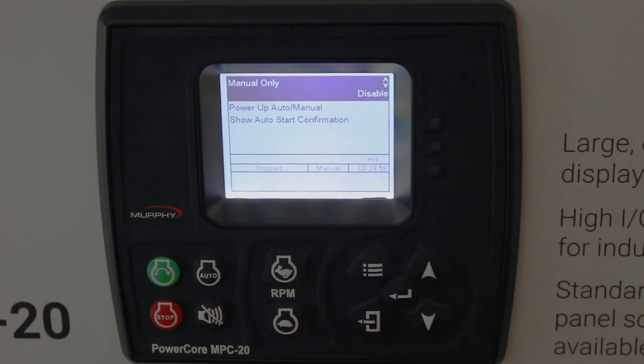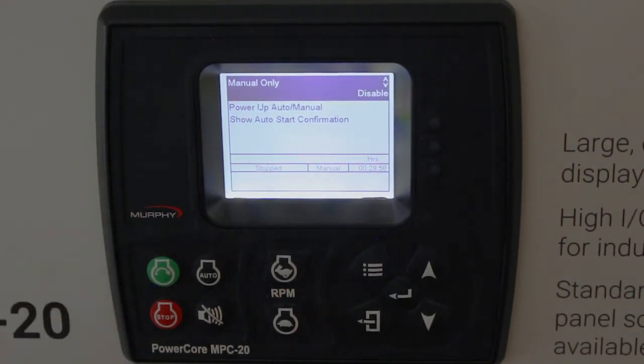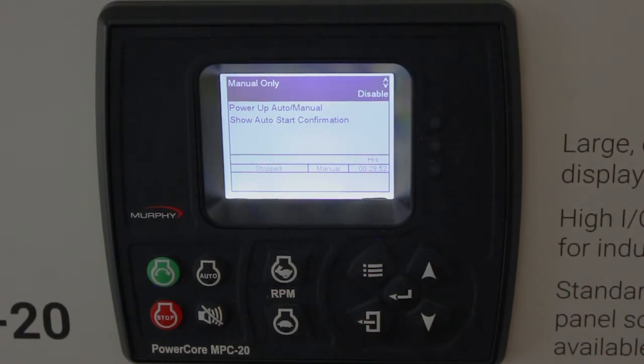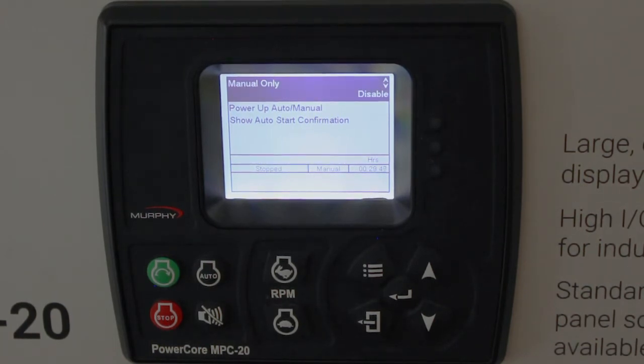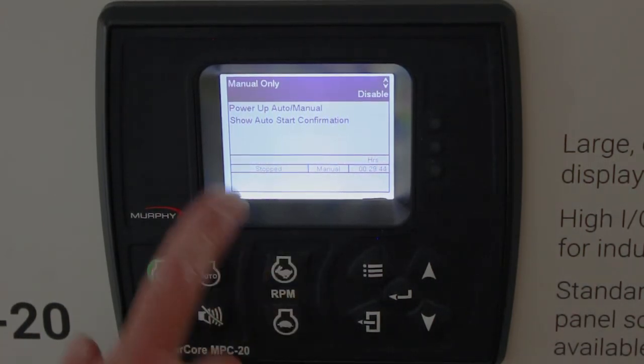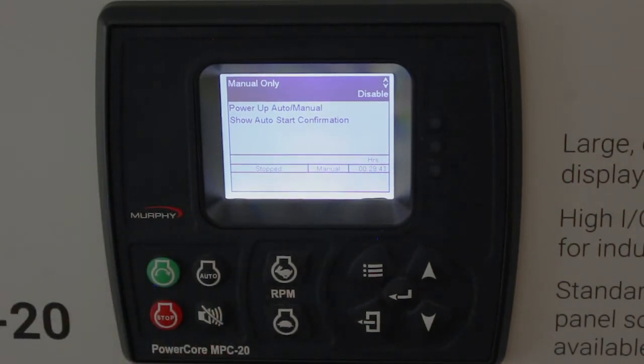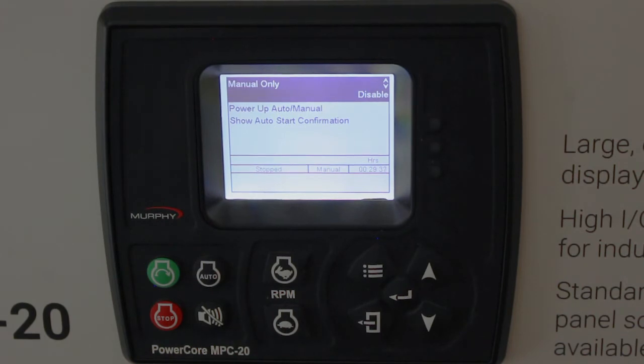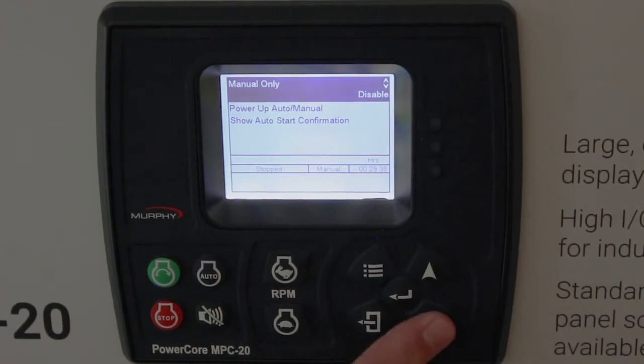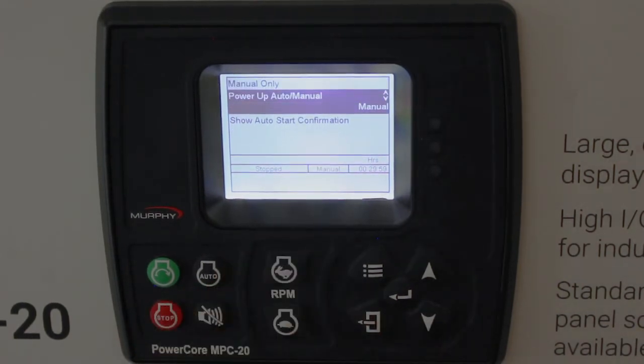Auto/manual — the first set point here allows you to have this controller just be in manual only and disable auto altogether. It's disabled by default, but if you set it to enabled, it would only work in manual. Power up auto or manual — when it initially powers up, if you want it to go straight to auto or straight to manual, you can do that. It defaults to manual.